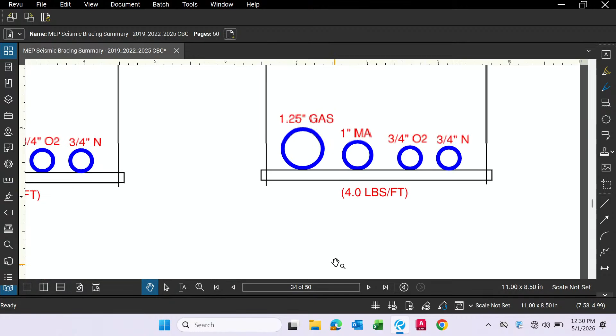This one. Same, we're still in the same building, a risk category 4 building. Come on. I would say yes. Yes? But why is that? Because it's a category 4. And, well, I know that pipe right there is bigger than 1 inch. And it's hazardous. That's correct, you're absolutely correct. So, two things here. Risk category 4, again, this pipe right here has an importance factor of 1.5 based on two requirements. It carries hazardous content, so 1.5, and it's in a risk category 4 building, so that makes it 1.5 also. Because of that, it needs to be braced.